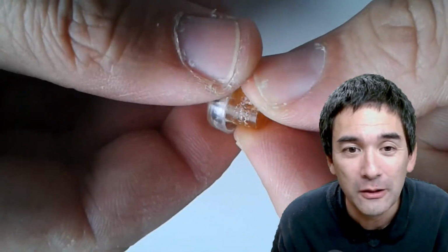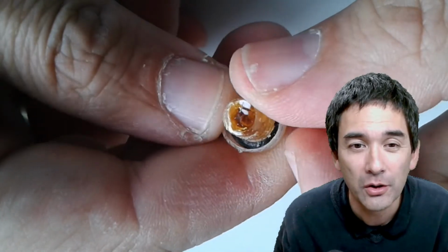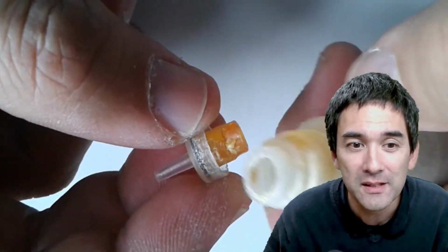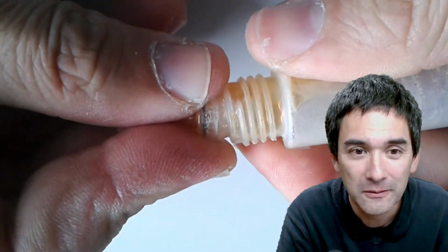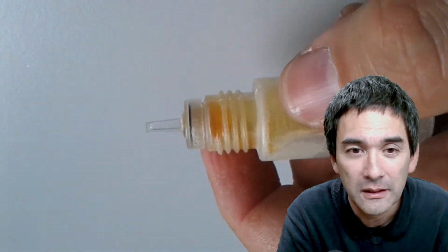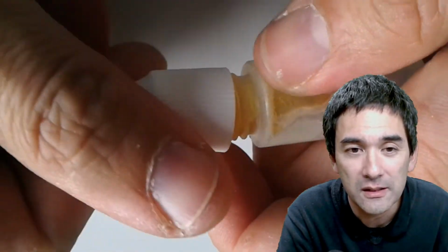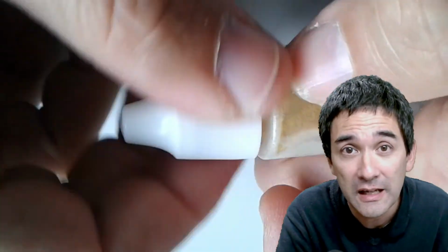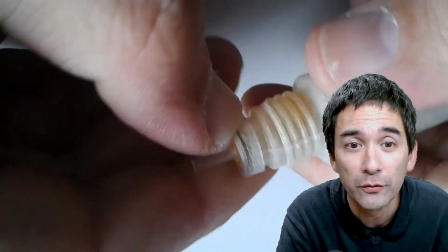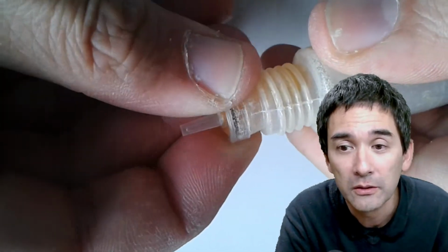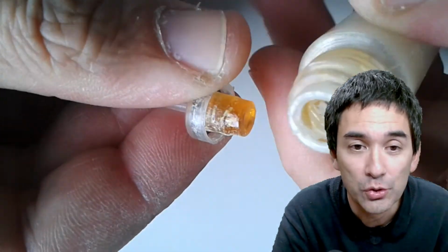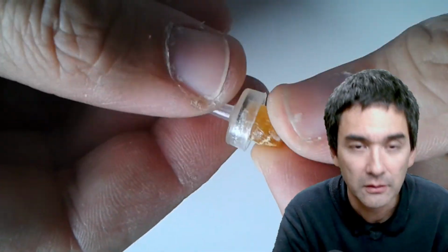It has turned completely hard because certain solvents in the oil have evaporated, and this immersion oil has never been used. This was actually one of the bottles in school. It tells us that, especially when using natural immersion oils, we have to clean it off. Otherwise, there is the danger that the oil will turn solid. But this does not happen with the synthetic immersion oils. Just so that you're aware of that.